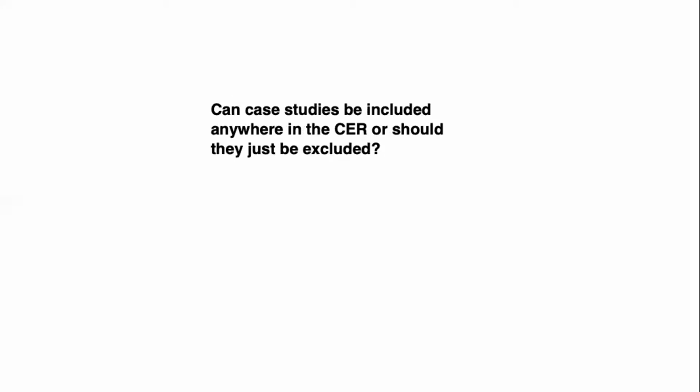For example, if you read a case study for a coronary guide wire, and that case study references that your coronary guide wire was used in that procedure, and that case study also says the procedure was successful, then you can extrapolate that conclusion as data.